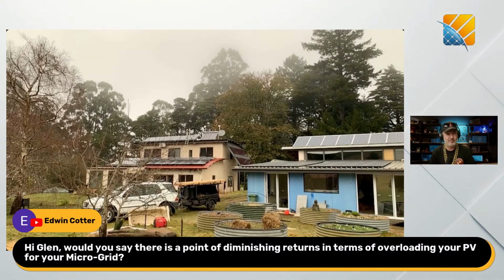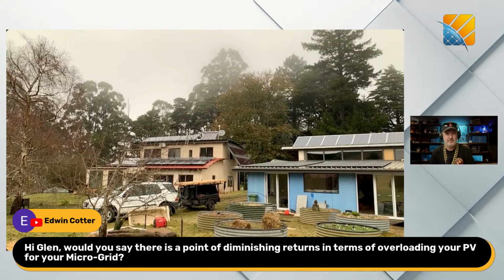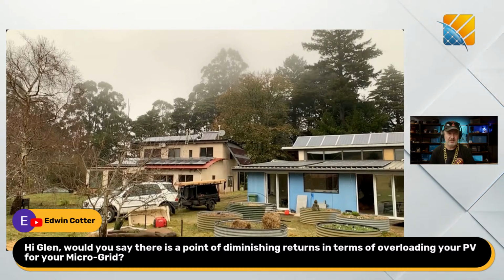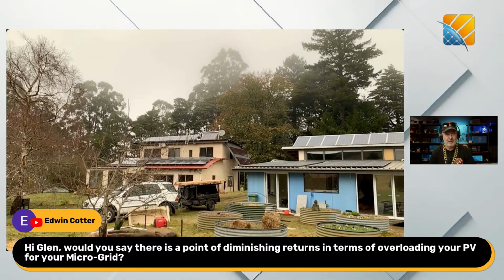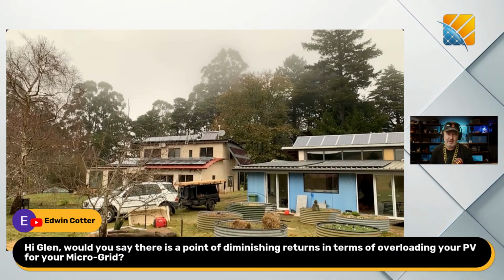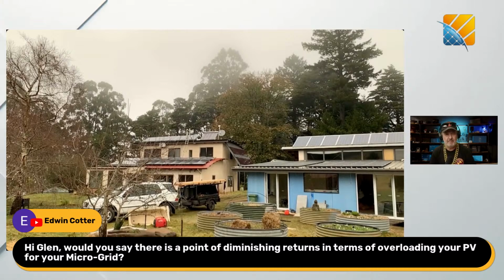Well, it all depends what those returns are and what the cost factors are. There are ratio limits when it comes to how much overpowering you can put onto a system. One would be the maximum charge current you can put into a battery system, which needs to be limited to suit the battery manufacturer's requirements. But also, if you have an AC coupled system, the ratio of solar inverter power to battery inverter power has to be considered. Many manufacturers will give you a number, typically 1-to-1. Some will let you go beyond that, but it does become a bit of a hard limit.